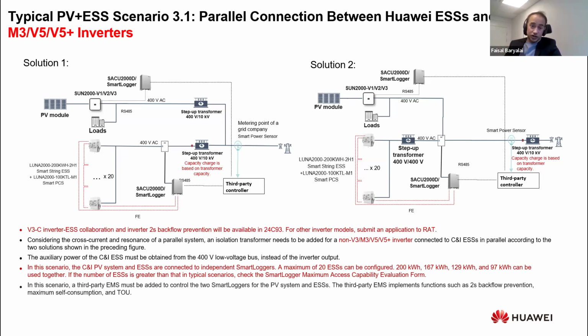So this is the condition when you have non-compatible or other brand inverters—you need an isolation transformer. But the isolation transformer also has other functions or benefits. For instance, if the grid collapses, the inverter will work efficiently even if the load is unbalanced, because the isolation transformer separates the inverter, the PCS sitting on the Luna battery, from the load.